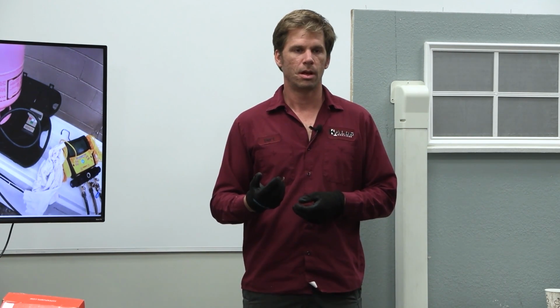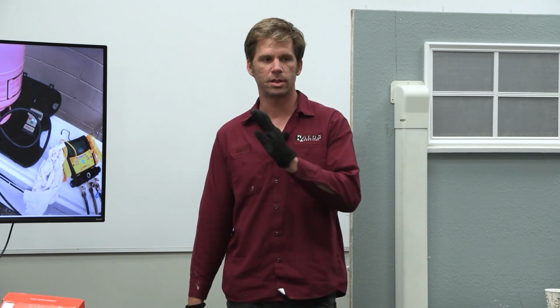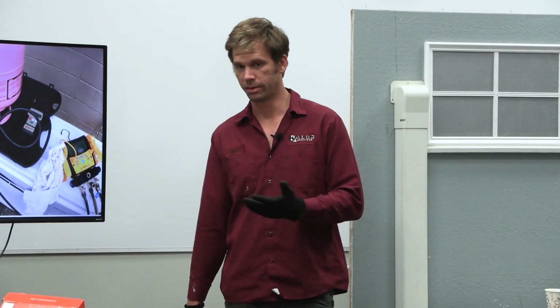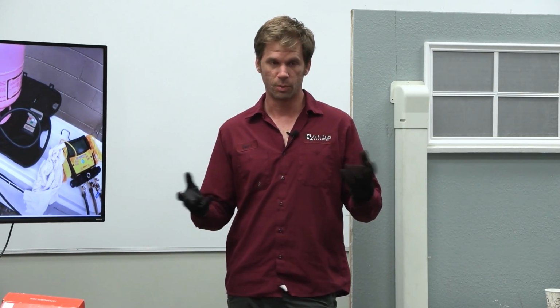Now, oftentimes they're a little hard to get to on the bottom side without a flashlight and a mirror. So always have your flashlight and your mirror right there with your little bubbles when you're testing that. And in the meantime, the system is sitting. You're watching the PSI, making sure that it's not actually dropping under that pressure. And then you're safe to go ahead and hook up the vacuum. Now, a vacuum on a ductless system is such a small area, they'll pull down really quickly, which is great. That's nice. You take out your Schrader core.